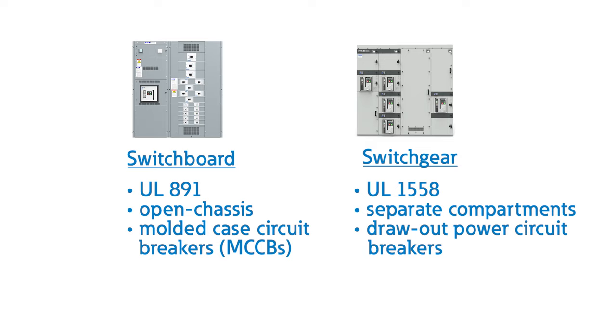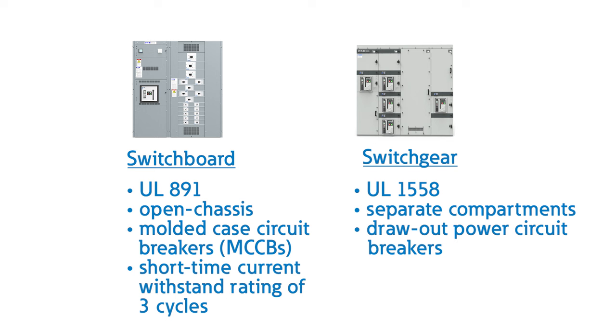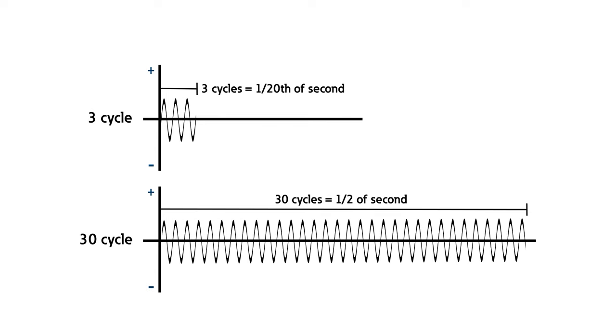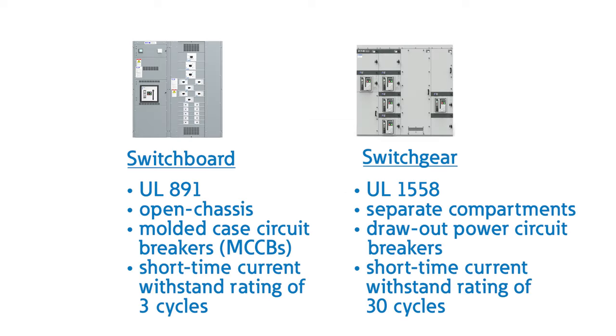Another major difference is short-time current withstand rating. A switchboard generally has three cycles for selective coordination with downstream components before tripping, and switchgear is rated to withstand 30 cycles. This extra time allows for coordination with downstream devices.